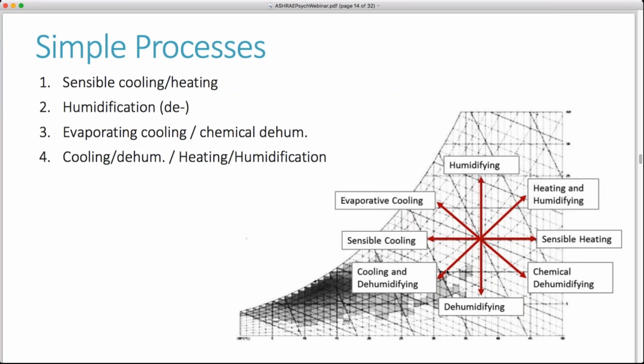Cooling and dehumidifying, down here, involves the removal of water from the air as the temperature falls below the dew point. Evaporative cooling or free cooling involves the cooling of air without heat loss or gain. Sensible heat lost by the air is converted to latent heat in the added water vapor. This is also called free cooling since it doesn't require any mechanical DX cooling.